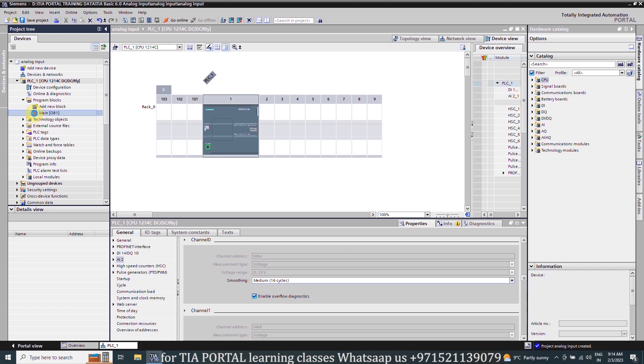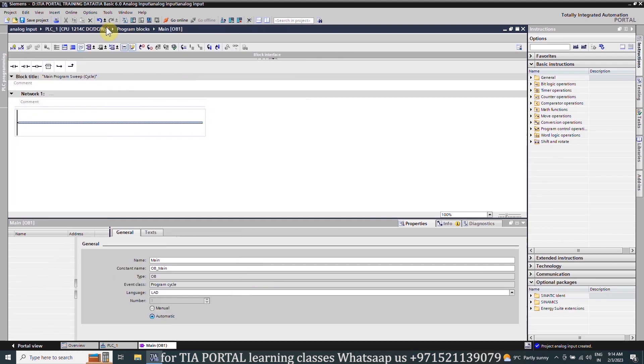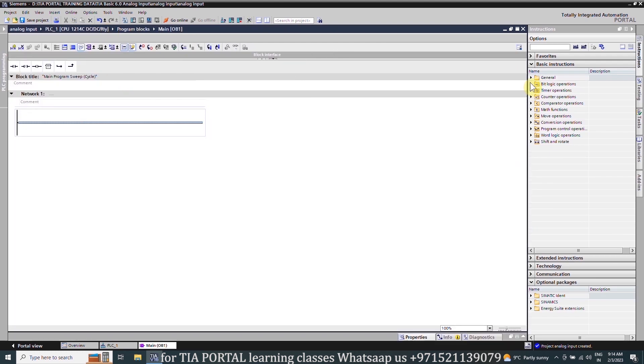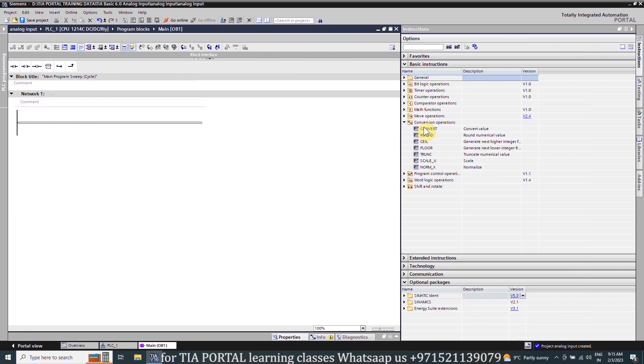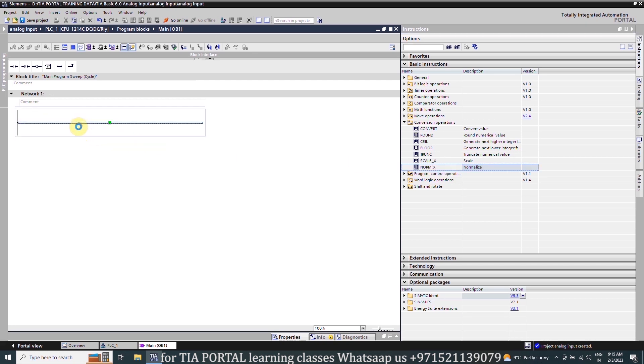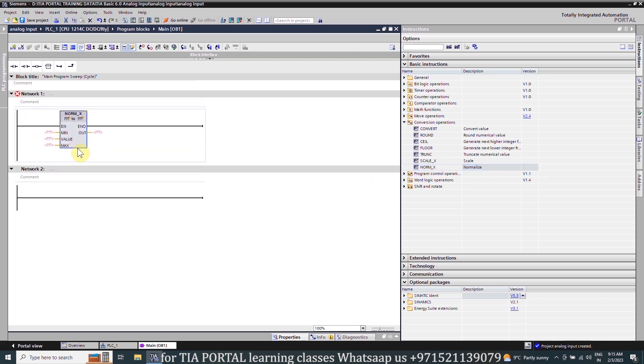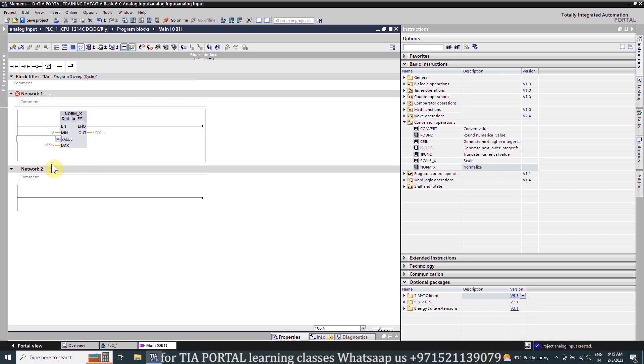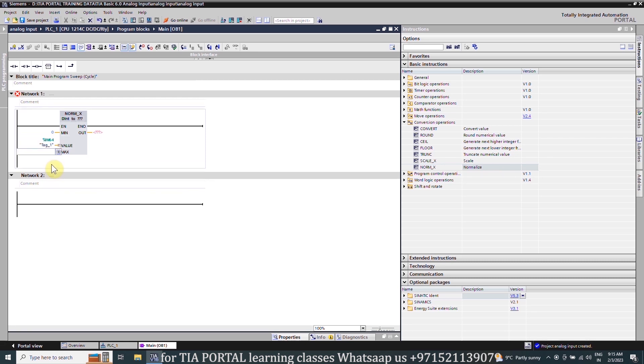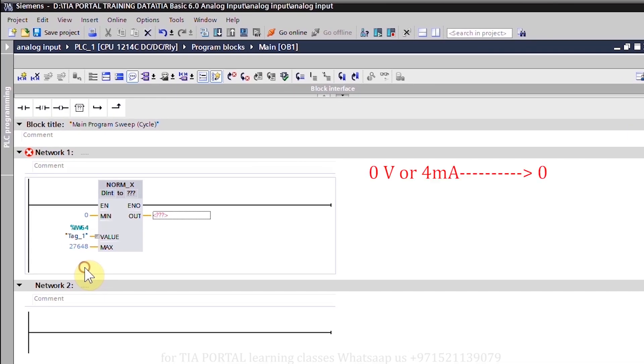Next we will go to the program blocks and open the main block OB1. We will open the conversion operations and drag and drop the NORM_X function. Here we will select the double integer input, and the minimum value we will insert as 0. In the value input we will insert the IW64 which is our analog input channel 0. In the maximum value we will insert 27648. At 0 volts input our PLC will understand it as 0, so we have entered 0 in the minimum value, and at 10 volts our PLC will take it as 27648 value. That's why we have entered this 27648 value in our max input.